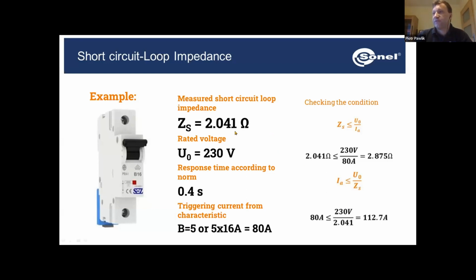So we got the fault loop 2.041. Is it good or bad? Okay, so we take our supply voltage, which is 230 volts, divided by 2.041 ohms, and that gives us the value of 112.7 amps. So this will be the value of current flowing in our circuit in case of a fault situation. Now, is it going to trigger our B16 MCB? Well, yes, because B16 is triggered by 80 amps in 0.4 seconds. So our fault current is higher than the current triggering our breaker.